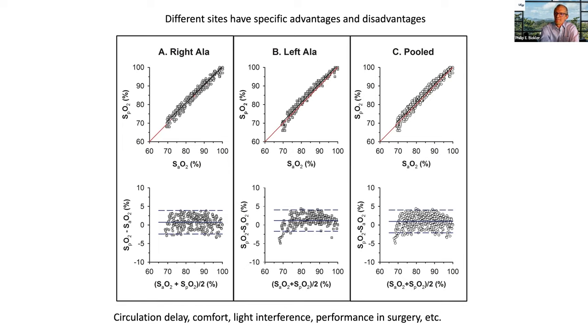One way in which this relationship is analyzed is depicted in the three graphs on the bottom. This is called a Bland-Altman analysis, where it presents the difference between what the pulse oximeter sees and the true value in arterial blood, versus the saturation level. This can show the errors in this method of pulse oximetry, and it's a widely used method for describing errors in other types of medical monitors, and it's the standard for pulse oximetry assessment.